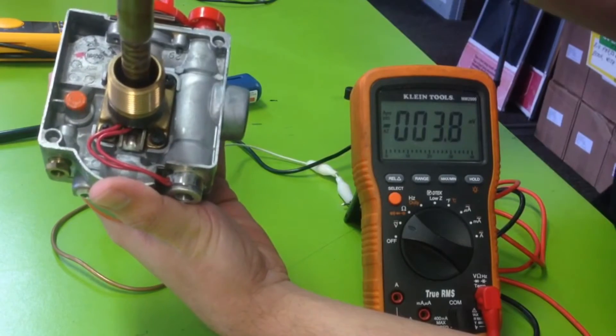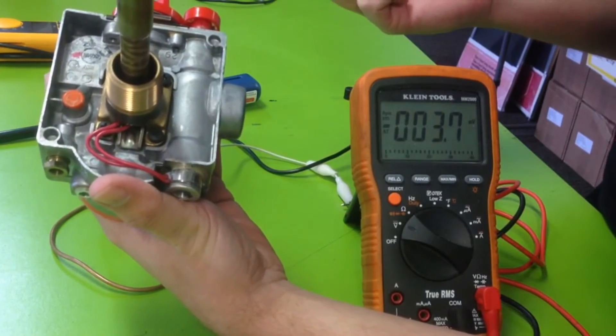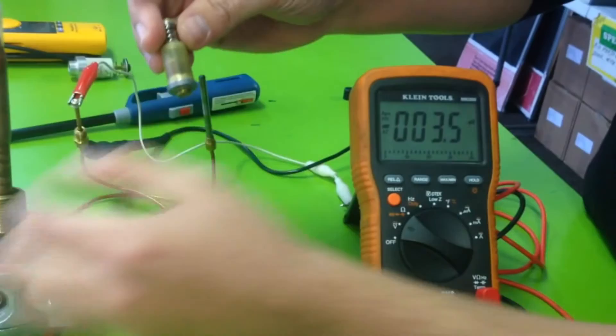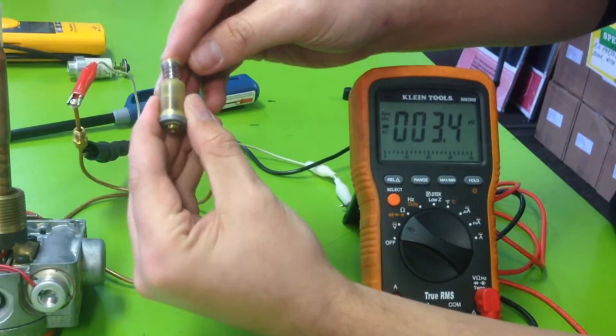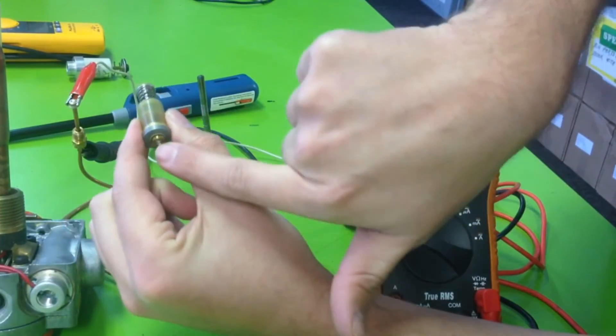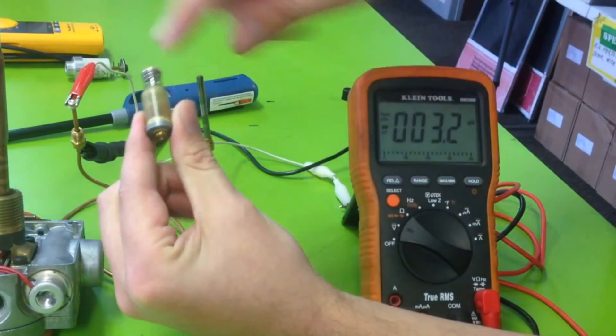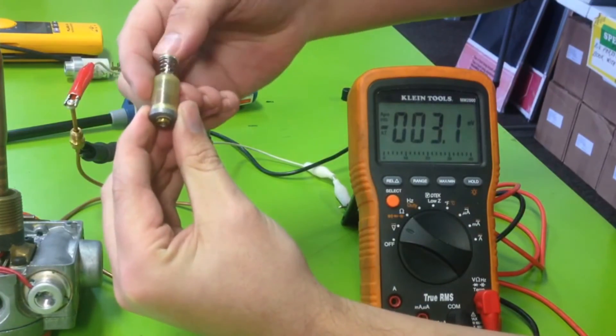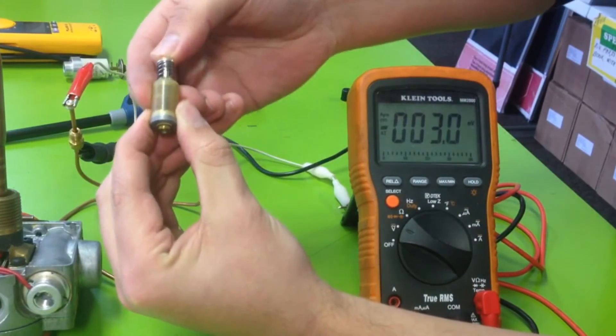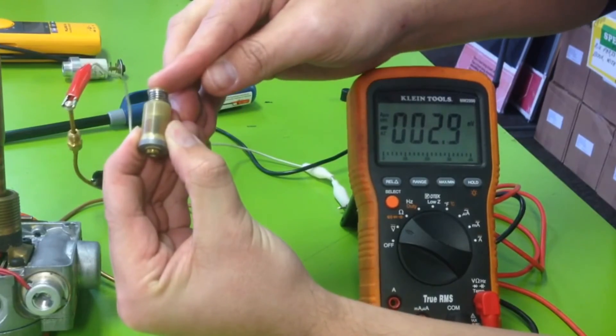That's a really quick easy way to diagnose this. So this is the internal piece - not sure how good you can see this, but how it works is when those millivolts are generated, it powers this little coil in here which makes magnetism, and that's actually what holds this down and lets the gas flow.